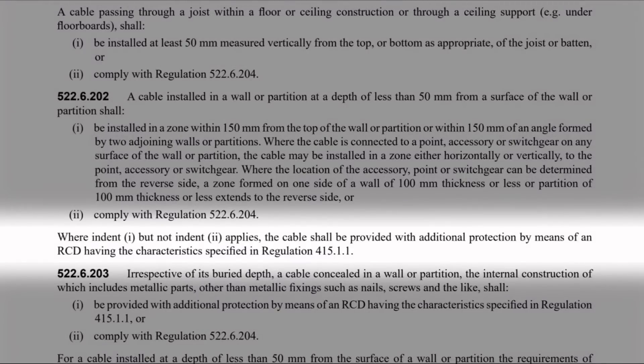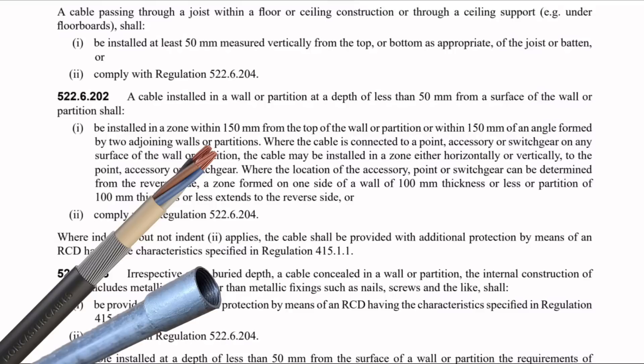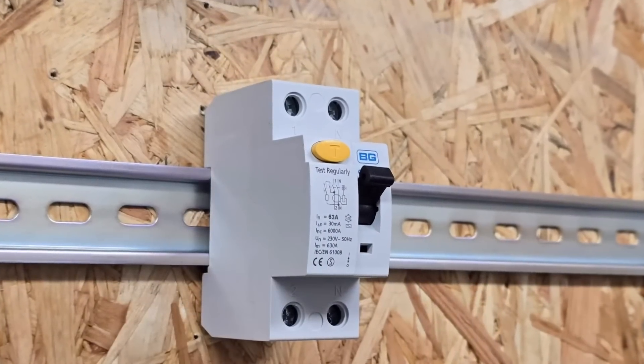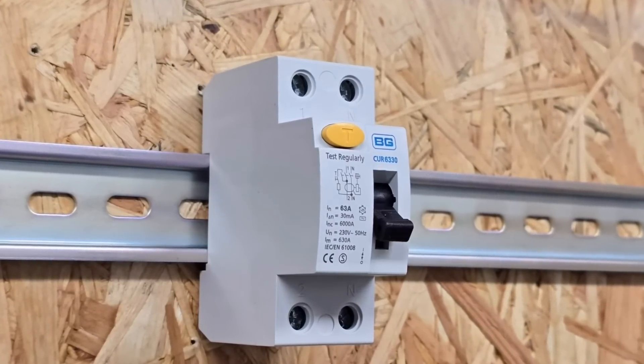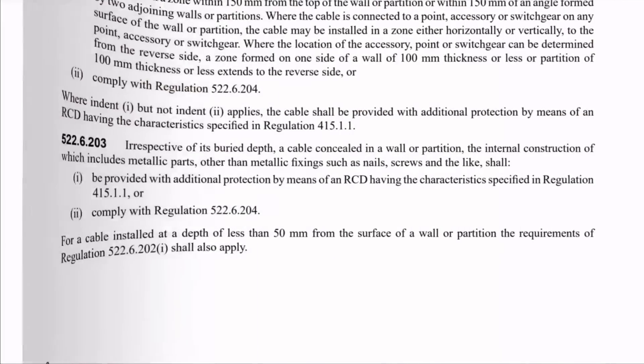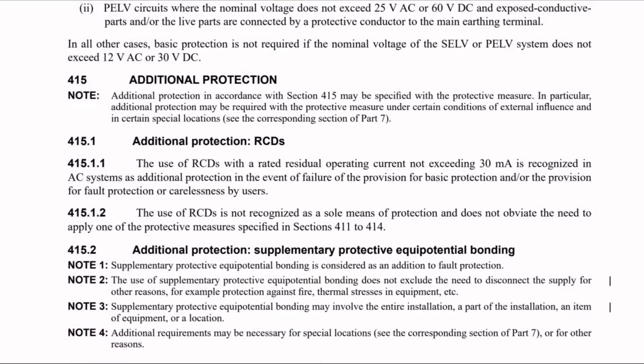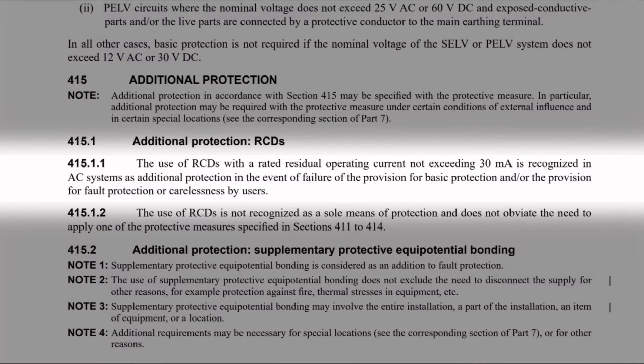Where indent one but not indent two applies, the cable shall be provided with additional protection by means of an RCD having the characteristics specified in regulation 415.1.1. So if our PVC insulated twin and CPC cable is buried less than 50mm deep in the wall and doesn't have extra mechanical protection, we need an RCD. This is so that if someone accidentally drills or nails into a cable, the RCD will protect them if they receive a shock. Regulation 415.1.1 confirms: RCDs with a rated residual operating current not exceeding 30 milliamps are recognised in AC systems as additional protection in the event of failure of basic protection.